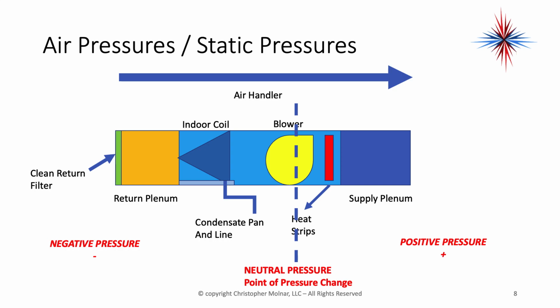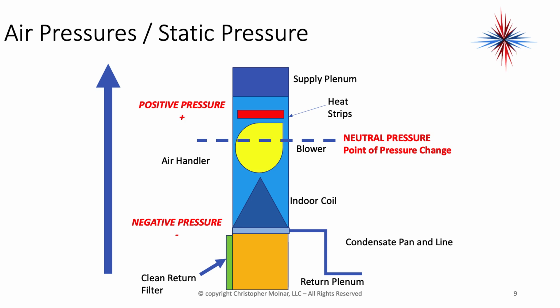Now, what we really want to be talking about here is static pressures. That's the air pressure that is occurring inside the systems. On the return side of the system, everything is negative, so we call it the negative pressure side of the system. Our neutral pressure, the point of pressure change, and again, this is air pressure, not refrigerant pressure, is going to be that blower. The blower is my point of pressure change. Everything on the outlet side of the blower is going to be a positive pressure. So our coil, condensate, filter, and return plenum are all on the negative side of the system. Our heat strips and supply plenum are all on the positive side of the system. Our point of pressure change, or the neutral pressure, is the blower. Again, in an upflow system, it's basically the same way: negative pressure on the return side of the system, blower neutral pressure, positive pressure on the supply side of the system. This becomes very important when we start talking about pressures.